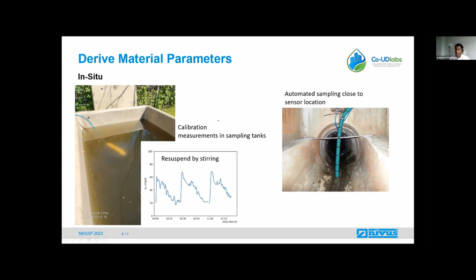And once you have all this, you can think about really doing measurements. You have the characteristics of the transducers in your sensor, you have first ideas or good approximations of the material parameters, and then you can collect data on the overall concentration of TSS. And as you see here, it resolves nicely the dynamics that exist in the channel. For example, on the left, we see that the TSS inflow increases, and the discharge increases with a little bit of a time shift, at an inflow of around 600 liters per second. A similar picture with an inflow of around 600 liters per second gives a much different inflow in TSS and also in discharge.